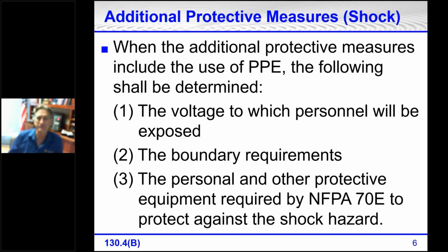All right, so when we're determining additional protective measures for shock, what do we have to know? Well, we have to know the voltage to which personnel will be exposed. We have to know the boundary requirements. Remember, I said the boundary requirements, we have two. We have the limited approach boundary, which is the furthest away. We have the restricted approach boundary, which is the closest of the two boundaries. Number three, we also have to determine the personal and other protective equipment required by NFPA 70E to protect against the shock hazard.